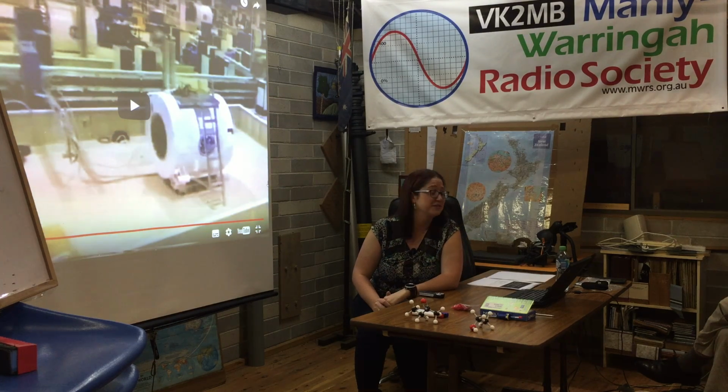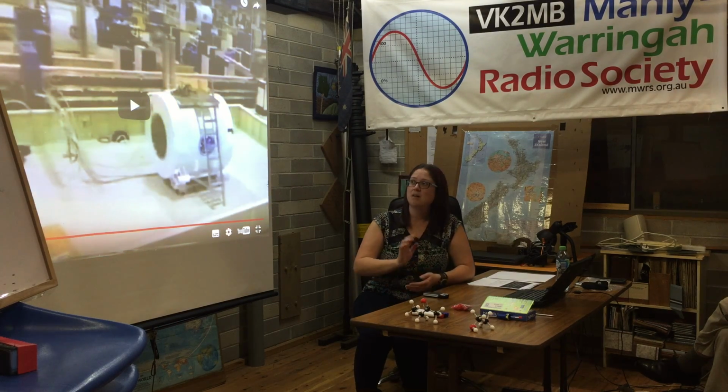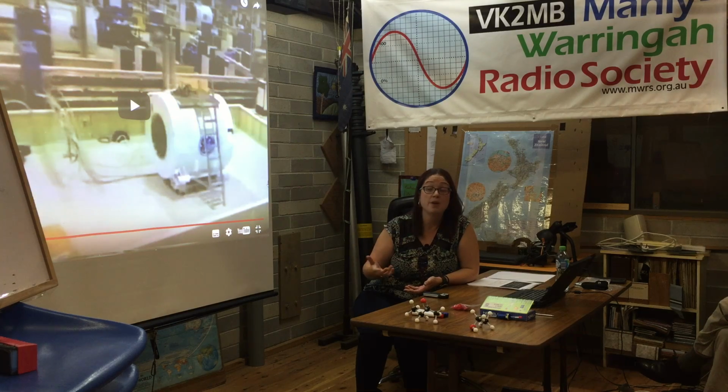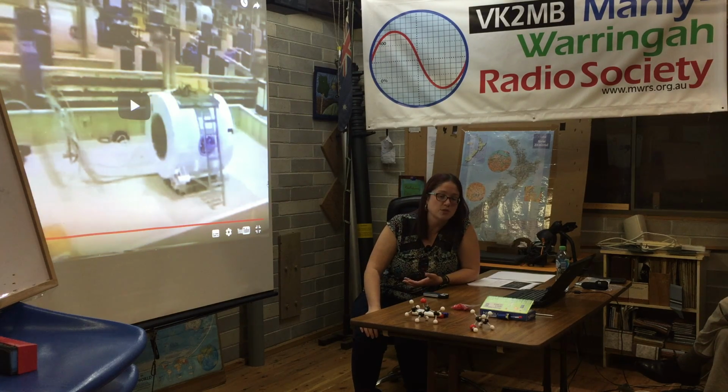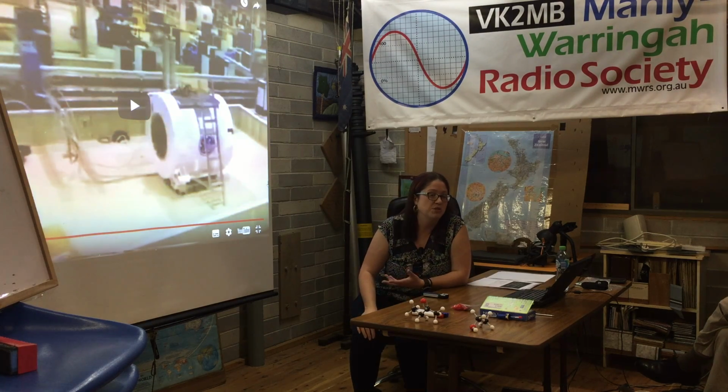There are also some pretty horrific examples of medical catastrophes that have happened when you take these sorts of objects close to these magnets. So the video introduced the idea of superconductivity and the fact that you have essentially a solenoid, you're passing a current through a wire, a coiled loop, and generating a magnetic field, huge currents in this case, in order to generate very high magnetic fields. And because these are superconductors, once you have charged the magnet, once it's at field, you don't supply any external power.